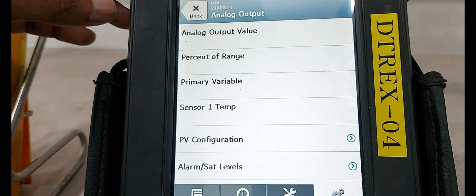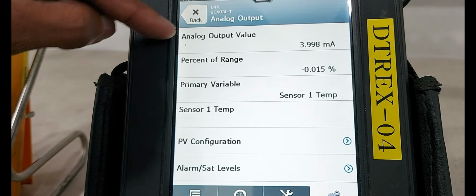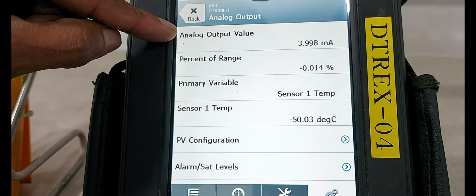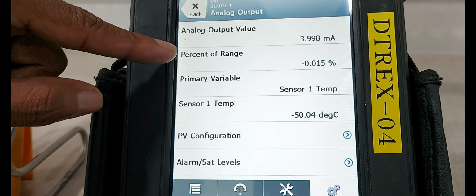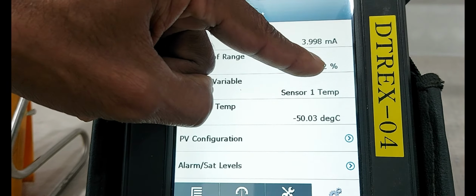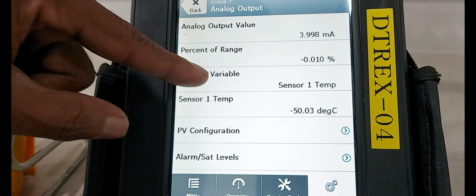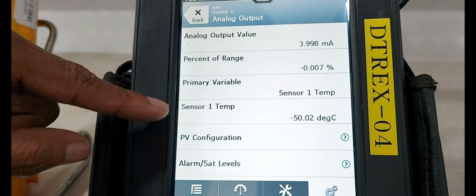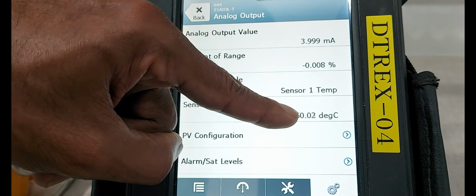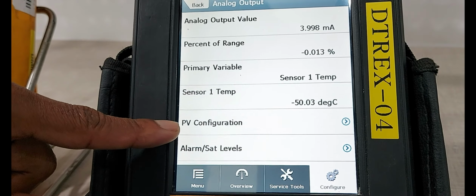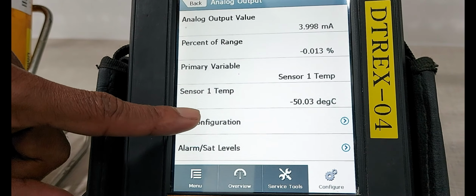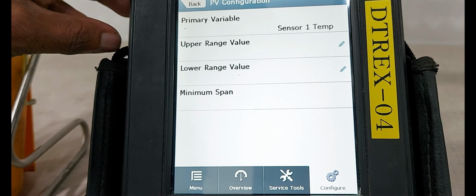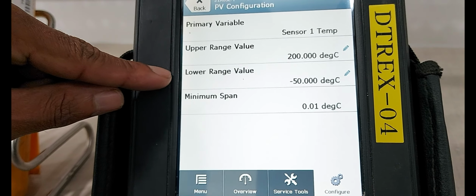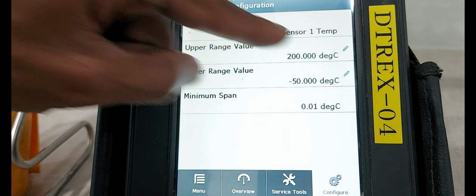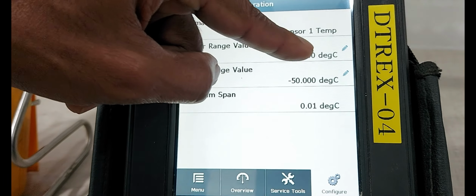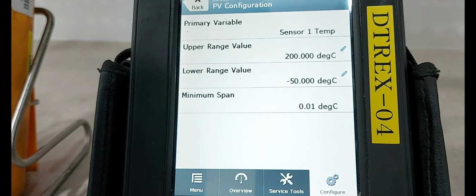Select it. Now display shows analog output is 3.998 milliamps. Percentage is minus 0.012 percent. Primary value selected sensor 1 temperature. Primary temperature is showing minus 50.02 degree. Next we are changing the PV configuration. In PV configuration we can change the LRV and URV. Okay, LRV range minus 50 degree. Upper range value is 200 degree.